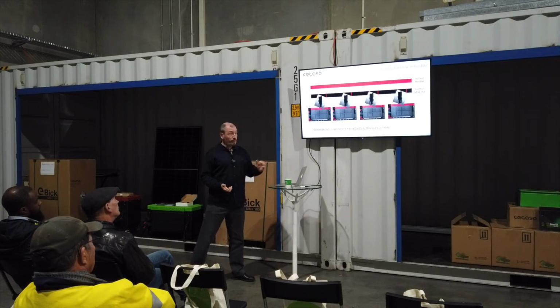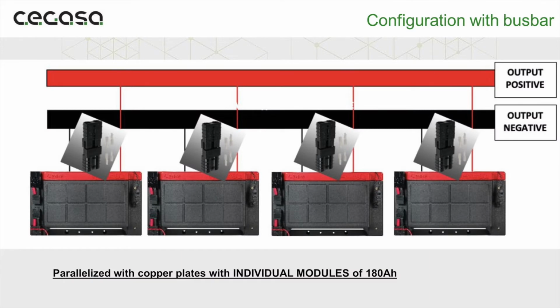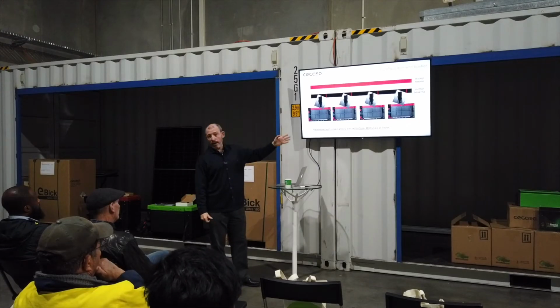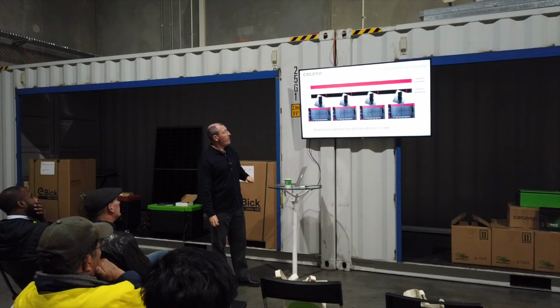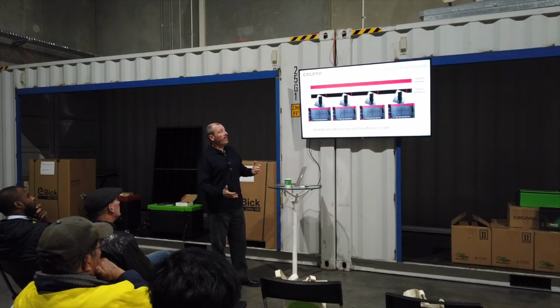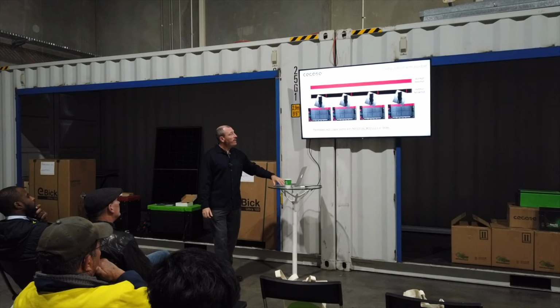How do you connect them? Again, we cannot insist enough, balancing the system is very important. So above 3 modules, we really recommend the use of a busbar. There are different ways to connect to the busbar. You can go on single items, as many modules as you have, connecting them one by one to the busbar, and that ensures they will be balanced.